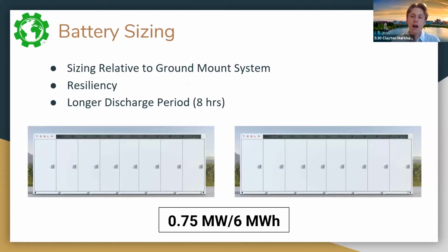Taking all this into account, we decided on a battery size of 0.75 megawatts and 6 megawatt hours. This sizing is more appropriate to the 1.2 megawatt ground mount system that we were directly connecting it to. It's on the high side of a discharge period, 8 hours of the battery's rated power, which shows our emphasis on resiliency.